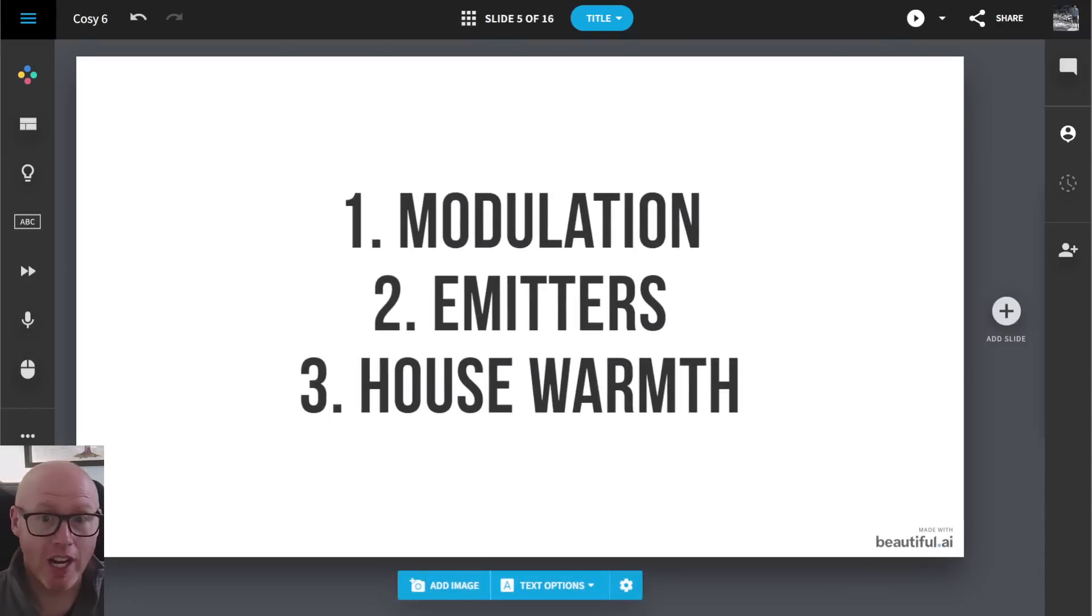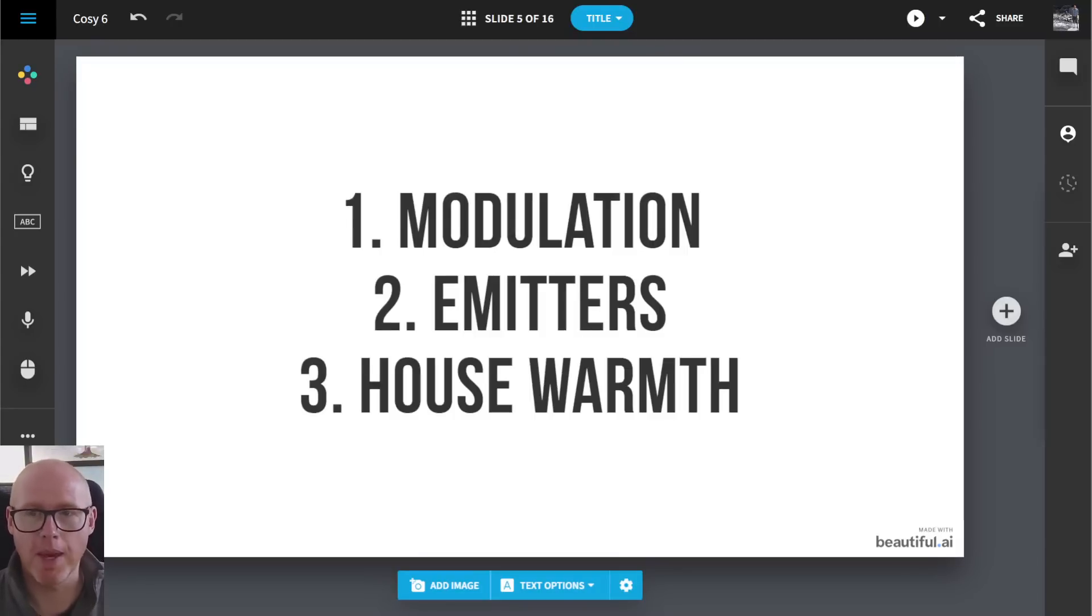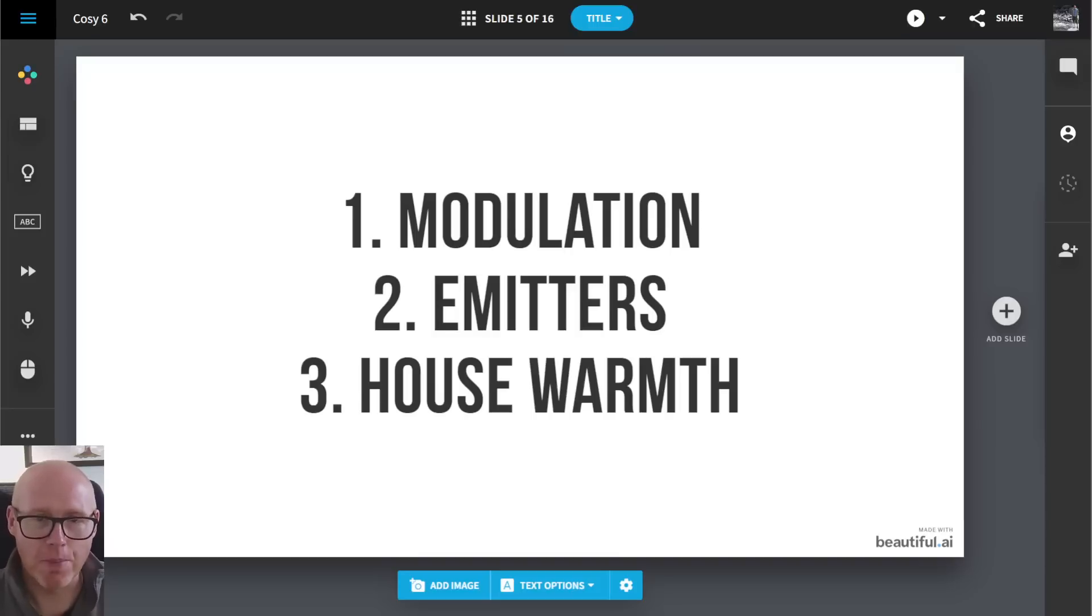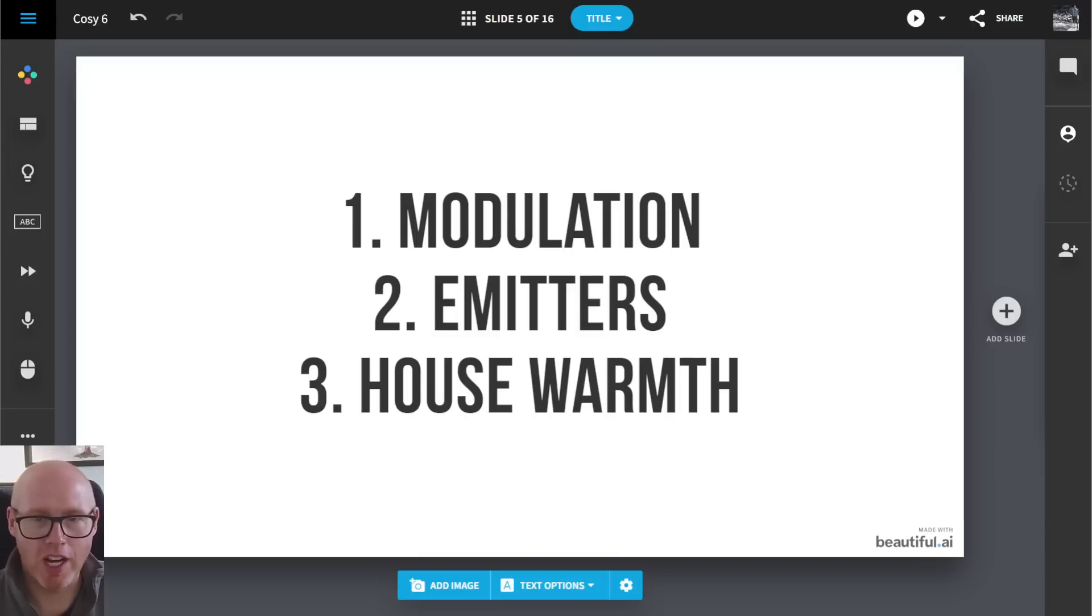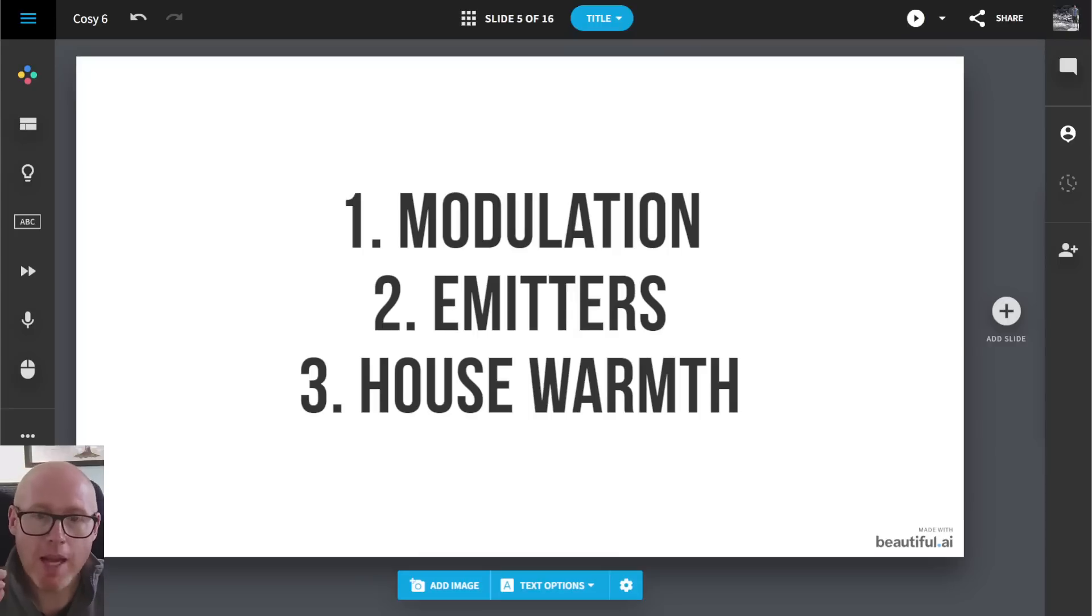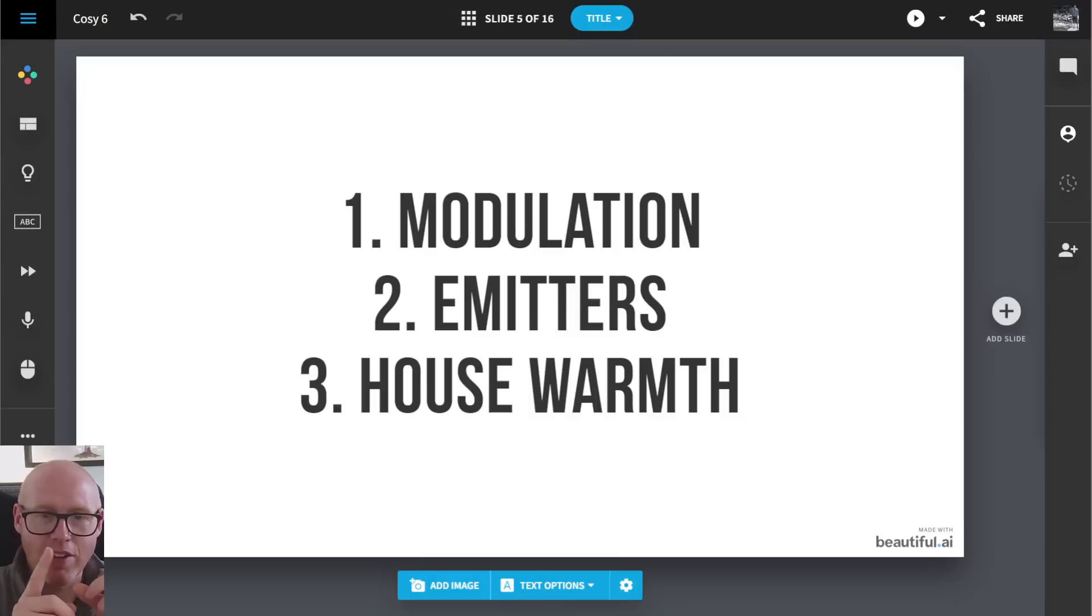There's a few issues with that. First of all is the modulation. Like I say, if the heat pump can't shed the heat through the emitters, through the radiators or underfloor heating, as your case may be, then all it can do is switch off. There's no point at running because it can't turn down the compressor any lower to put the heat in any more slowly. The minimum modulation rate on the Cosy 6 we expect is about 2 kilowatts. And so once it can't get rid of that 2 kilowatts, all it can do is it can shut off. It measures the flow and the return temperatures. And so it will know this heat isn't going anywhere. The delta between these narrows and it gets really, really, really close. And it basically shuts off.